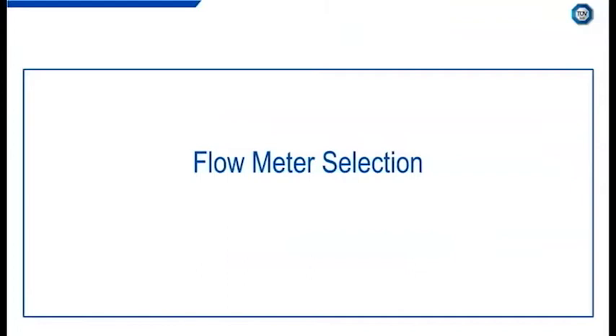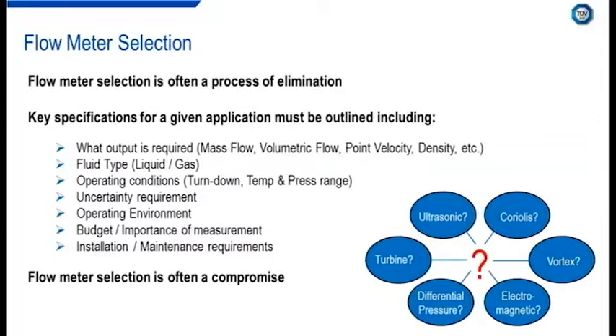So now that we have covered the fundamentals of flow measurement and some examples of metering technologies, we can start to discuss and think about considerations when selecting a suitable flow meter for a given application. So how do we determine the most suitable flow meter for the given application? Questions which should be considered when selecting a flow meter for any specific application include what output is required, as we mentioned earlier. Is a direct mass measurement necessary, in which case we discussed the Coriolis meter provides a direct measure of mass, volumetric flow, or perhaps density.